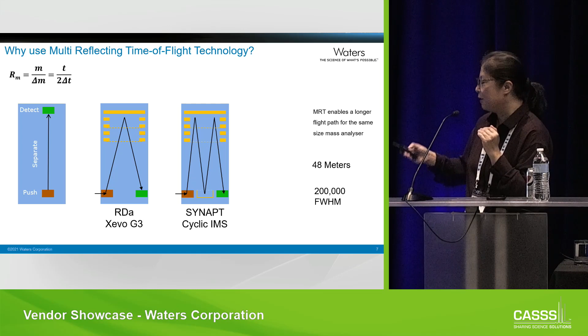And then later on, we have the W mode. Same analogy, but you kind of quadruple the flight path, therefore increasing the mass resolution by increasing the time of flight path. But those grids here, if you put a lot of grids here, you start to lose ion transmission. Each grid will only transmit about 92% of the ions. So if you keep building the flight paths using this method, you're going to eventually lose all your ions.